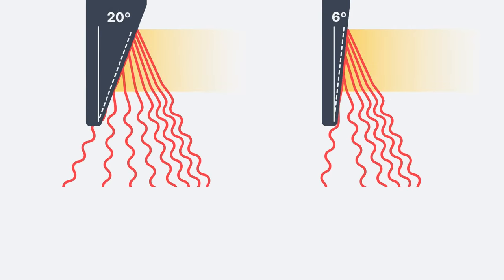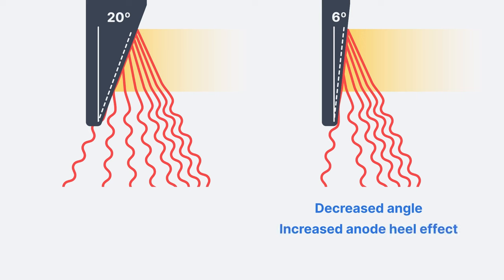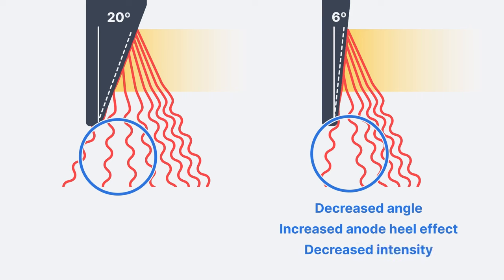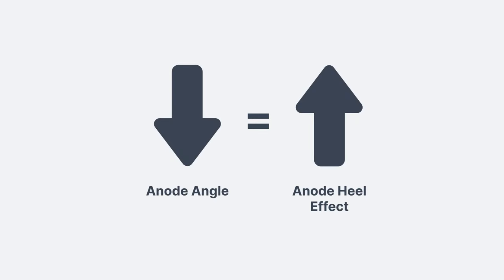A few variables can actually change the extent of the anode heel effect — in other words, the change in beam intensity across the beam isn't always the same. Here's one example: decreasing the anode angle, making it steeper or smaller, increases the anode heel effect. This is because more x-rays get absorbed in the anode and the beam intensity on the anode side decreases. You can actually see that happening: when we decrease the anode angle from 20 degrees to 6 degrees, an increased number of x-ray photons get absorbed in the anode. So there is an increased difference in intensity between the anode side and the cathode side. The relationship between anode angle and heel effect is inverse — as the anode angle decreases, the anode heel effect increases, meaning there will be an increased difference in intensity across the x-ray beam.